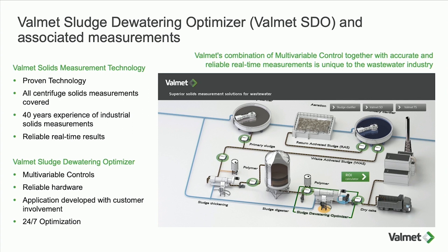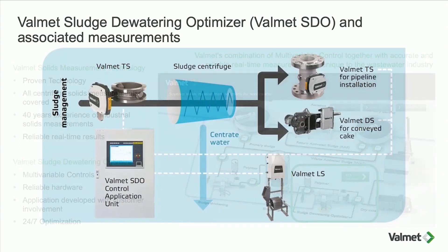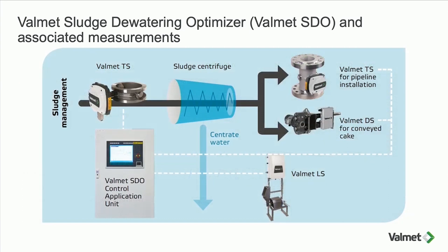We also have clever multi-variable controllers used within the pulp and paper industry, which we've developed so we can optimize and control the centrifuge in the wastewater process. The overall system is a combination of measurements and controls: solids measurements around the centrifuge — incoming, dry cake, and centrate — plus a control package with a multi-variable controller to optimize the centrifuge by automatically changing set points for polymer dosing, torque, and mass flow.